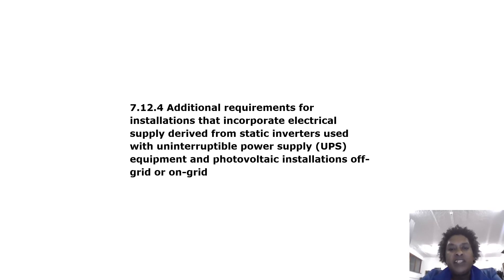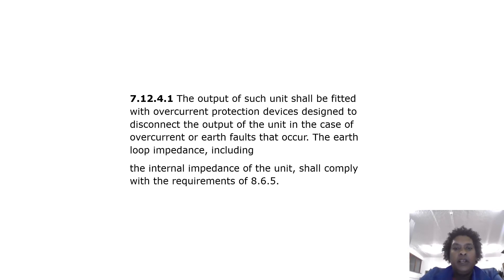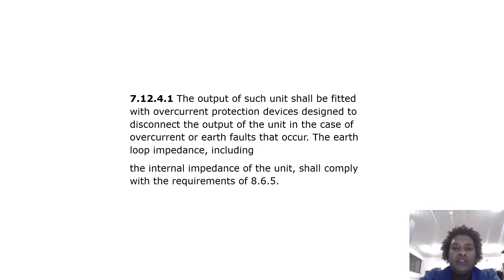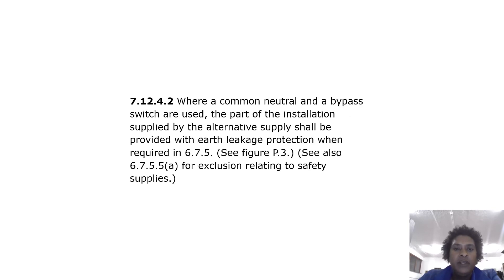Additional requirements for installations incorporating electrical supply derived from static inverters used with uninterruptible power supply equipment and photovoltaic installations (off-grid or on-grid): the output of such units shall be fitted with overcurrent protection devices designed to disconnect the output in the case of overcurrent or earth faults. The earth loop impedance including the internal impedance of the unit shall comply with the requirements of 8.6.5. Where a common neutral and bypass are used, the part of the installation supplied by the alternative supply shall be provided with earth leakage protection where required.